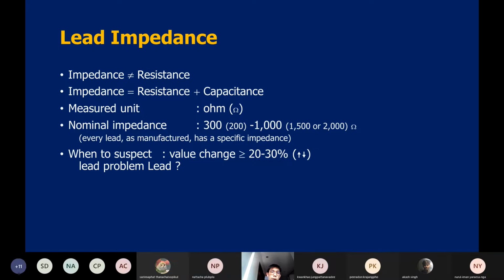This is an important term you need to know, and it is one of the indicators we use to follow up the leads after implantation. We call it the lead impedance. Impedance is similar to resistance, but it's not equal. Impedance is the resistance of the lead plus the capacitance of the lead. We use this impedance to follow up the patients, and if there is some change in the impedance, or it is not in the normal range, there must be a problem with the leads, either a lead fracture or an insulator break.